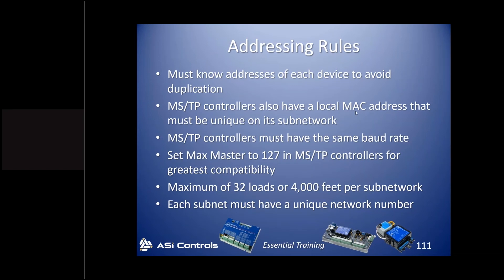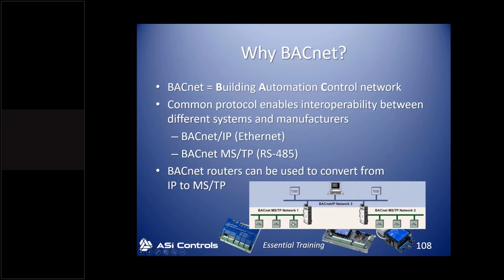Some settings are only relevant for MSTP, including the MAC address — which is very different from a MAC address on a computer's network card. In MSTP, you're almost always going to change the MAC address so that on any local MSTP network every device has a different MAC address. However, one controller on MSTP Network 2 can have the same MAC address as a controller on MSTP Network 1 because they're on different MSTP networks. In ASI Expert, all rooftop controllers have MAC address 1, and that's okay because they're on different MSTP networks.